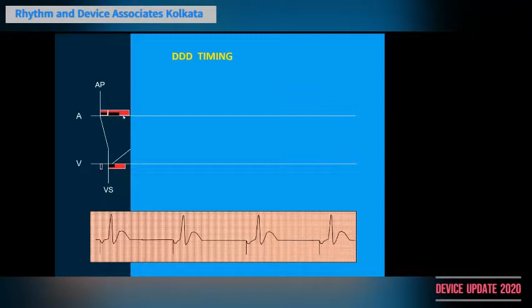I'll come to crosstalk later. So in the atrial chamber, an atrial refractory period is initiated. After the end of the atrial AV interval, if a ventricular sensed event is detected, a ventricular sensed event leads to inhibition of ventricular pacing, and it leads to starting off the two refractory periods that I was talking about.